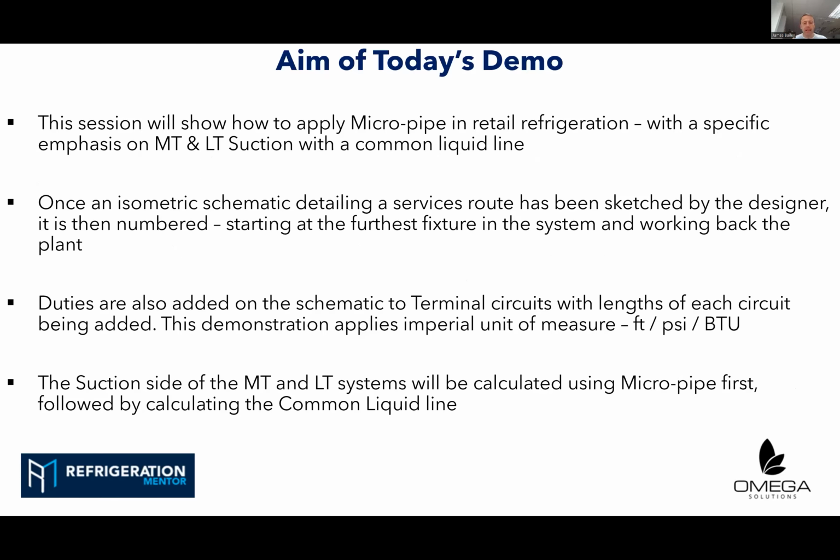So today's session, just to go back through, is going to show how to apply MicroPipe in retail refrigeration, and the specific emphasis is on medium and low temperature suction lines. And then I'm going to use the software to size a common liquid line. So there's some assumptions made, but they're on these slides.